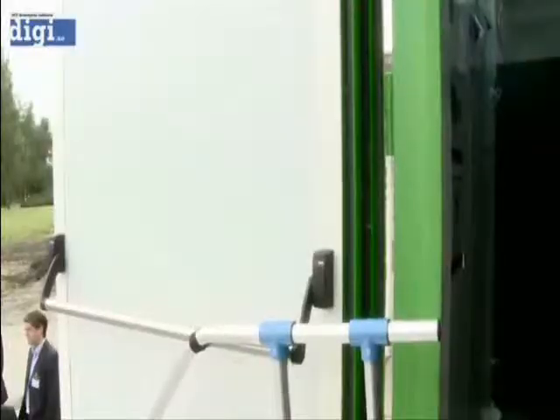We also, on all the doors, put a crash bar. So if you need quick exit, you can easily get out very quickly. You don't have to worry about those large, heavy end doors and trying to get those open, because once you're inside, you can't close those. These doors you can close and lock when you're inside, so you're maintaining your physical security as well as maintaining the environment, the temperature and humidity levels inside, which is very important to IT equipment. On larger containers, we would put multiple doors, so you have multiple exit points for safety.